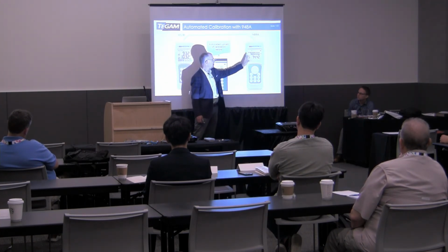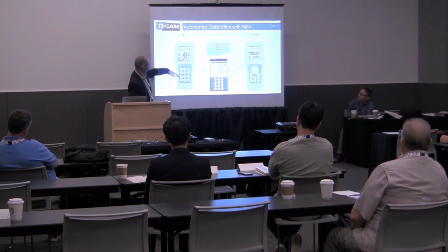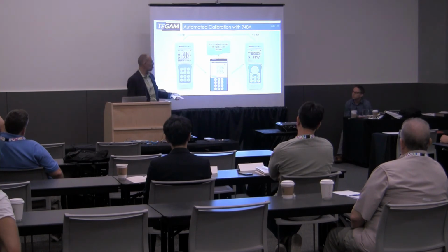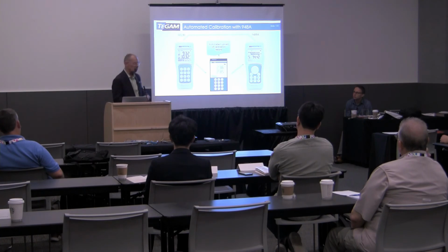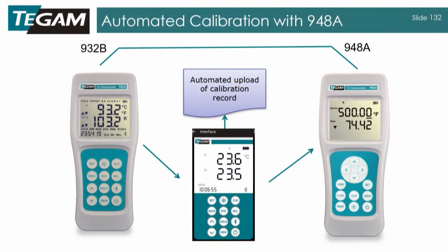It will talk to the calibrator, say, go to 500 degrees. This is the wired connection to whatever you're calibrating. If it happens to be one of our Bluetooth thermometers, it'll talk to this instrument, and you can automate the whole calibration process, and it'll email you back all the data, giving you serial numbers, data points, everything you calibrated, right back in your inbox, so you don't have to write anything down. You can go out in the field and do that.